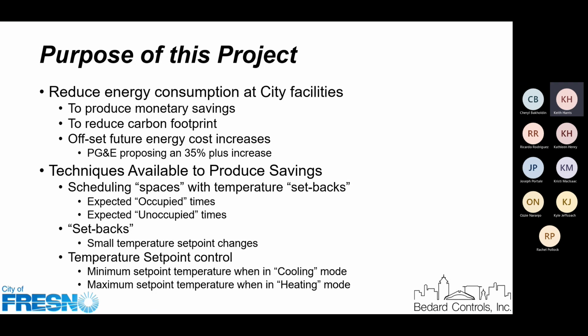And then the third is set point control, meaning you can only allow it to cool or heat the space to certain temperatures. And that's not the primary purpose of the project. It's really to schedule the spaces, then use setbacks to save some energy when not occupied. And third is to control the set point or the comfort level in the space.